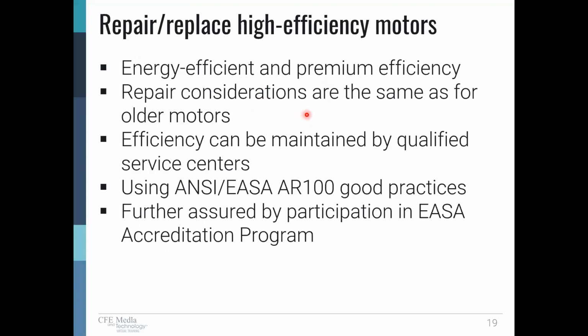We're trying to keep the efficiency level of the motor the same as what it was when it was built, really going back to day one. We want to preserve that. I don't want to say how it was received, because if the motor winding has failed, the motor doesn't work, and really it's basically zero efficiency.